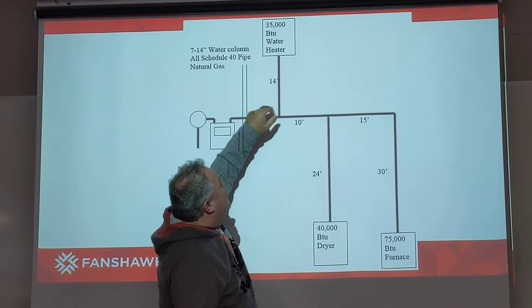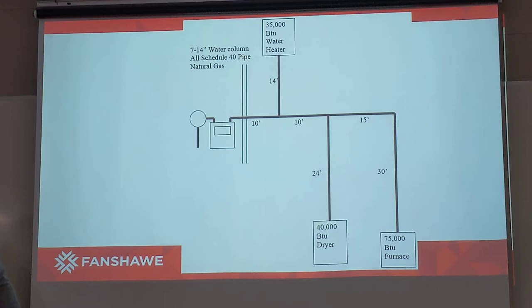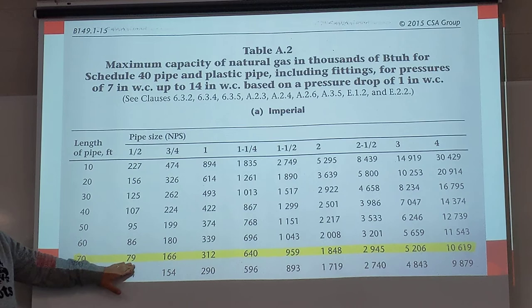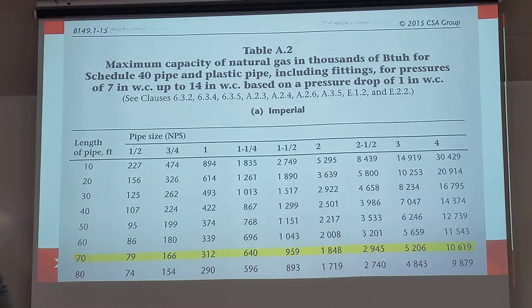Going up to the water heater off the main, we have a 14-footer that needs to serve 35,000 BTUs. We're still going to remain on the 70-foot code zone. Half-inch will work because the 79,000 BTU capacity well exceeds the 35,000 BTUs needed for that particular appliance.